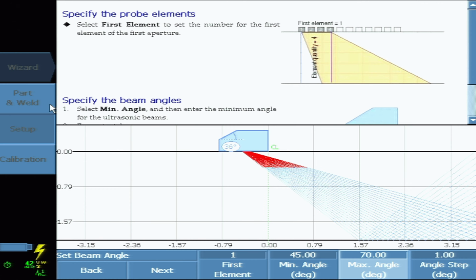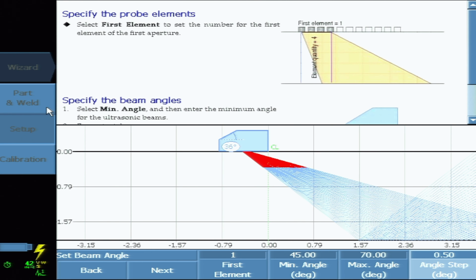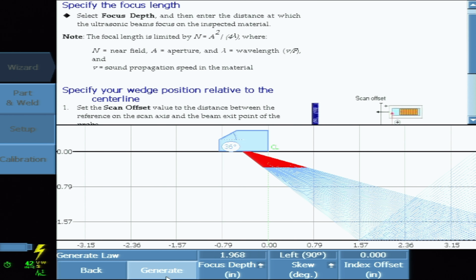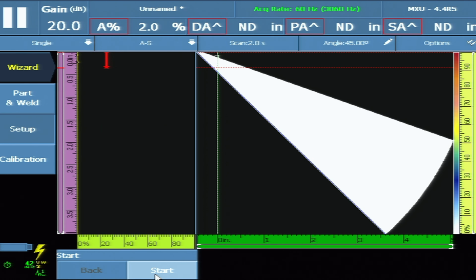These angle steps right here, we're going to set at 0.5. I like setting them at 0.5 instead of 1 because it gives you a little bit more forgiveness when you're measuring indications and stuff like that. We're going to leave the focus depth at 1.9 for now. And we're going to go to generate. It'll come up and you'll see angles 45 to 70 on your probe, as you can see.